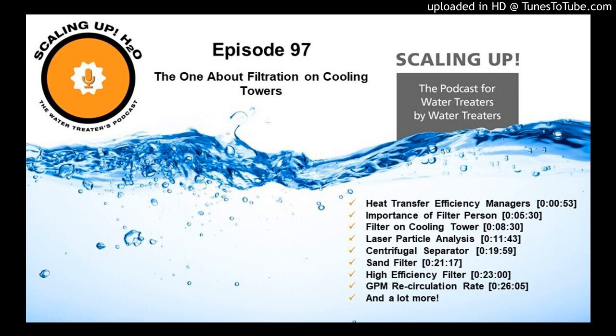So technically, I don't agree with using the sump sweep concept. It was a nice idea, and it actually helps people size filters because they just do it based on if they put a certain number of jets in the sump of a cooling tower, then the size of the filter is defined by that.